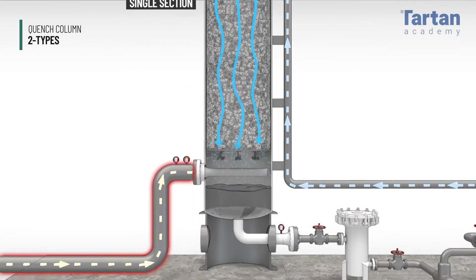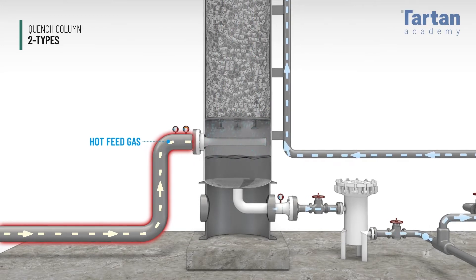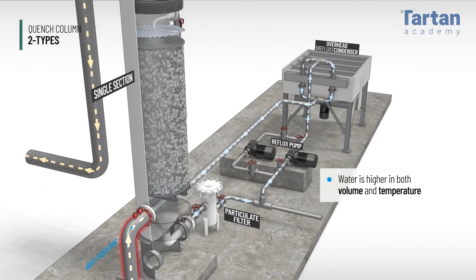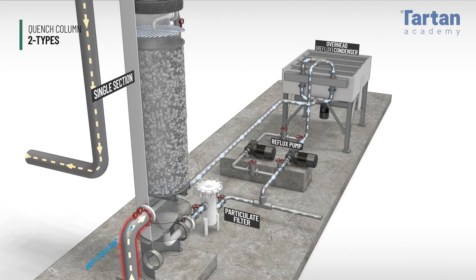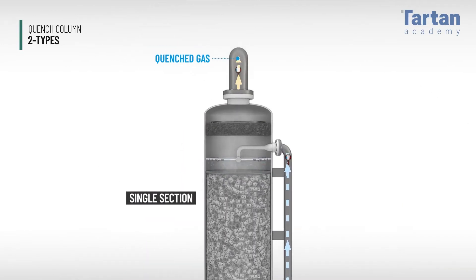As the gas is cooled, water is condensed and joins the circulating liquid. The water exiting the bottom of the tower is higher in both volume and temperature. A portion of this water is purged to the sour water stripper, and the rest is cooled and returned to the top of the tower.